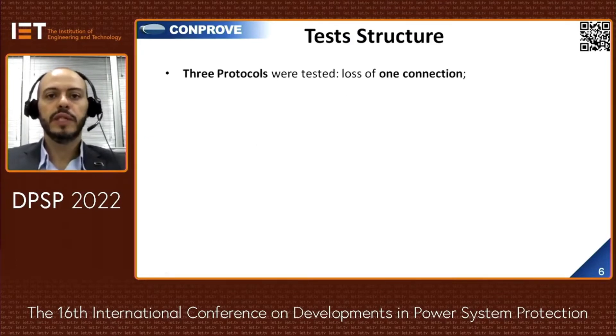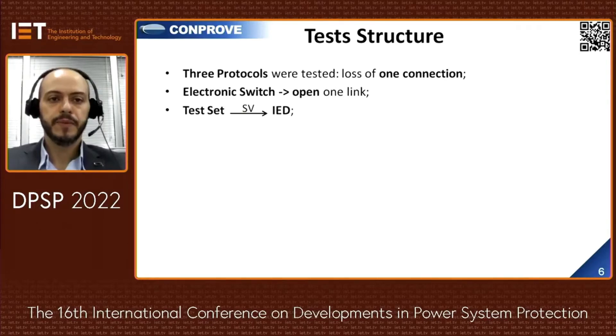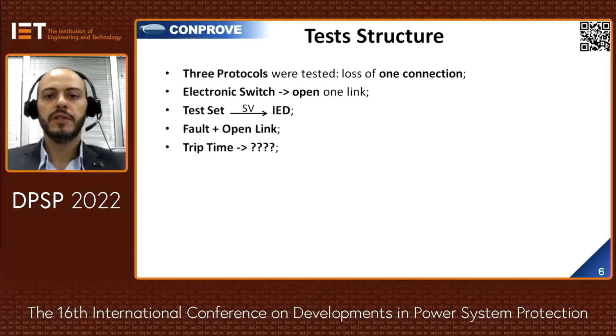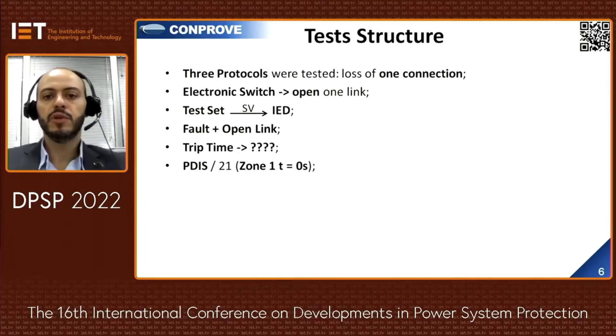The three protocols were tested considering the contingencies of link loss. The electronic switch opened the communication path, the test set published the sampled values, and the IED subscribed to them. The faults were injected at the same moment the link was opened, and the IED trip times were verified when this communication loss occurred in each redundancy protocol.